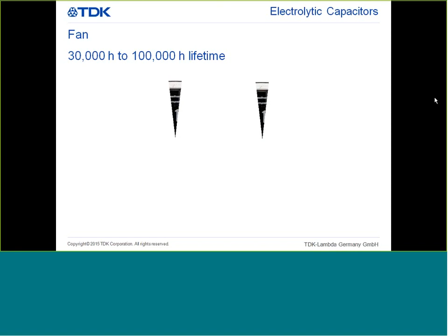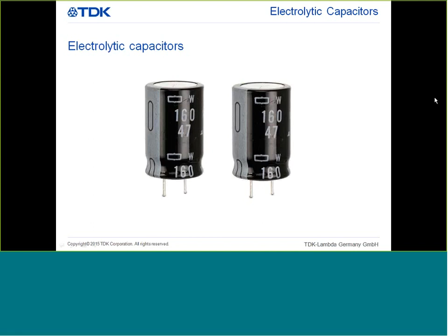The aging of the electrolytic capacitor depends mostly on its operating conditions. The temperature-related aging of e-caps is highest compared to all other components. Consequently, the electrolytic capacitors are generally the element that determines the lifetime in each power supply unit. Something all components have in common is that the lifetime depends upon the operating temperature. The hotter a component is, the higher the risk of failure and the faster it ages. The temperature is a key for a long life expectancy of each device.